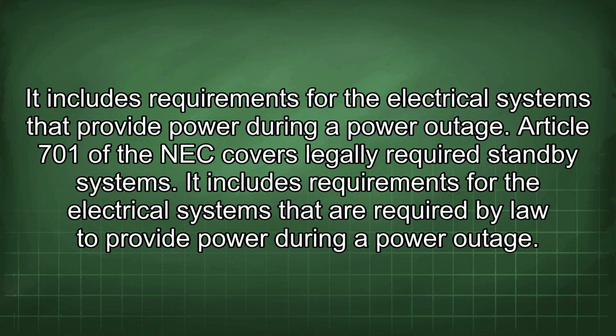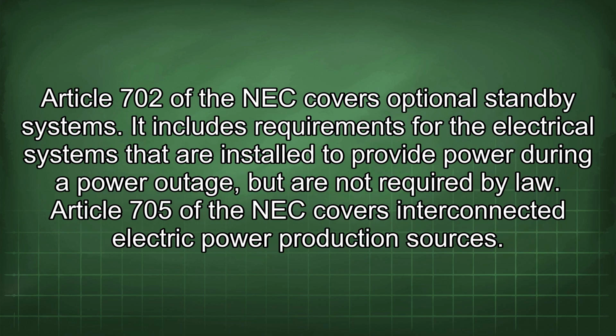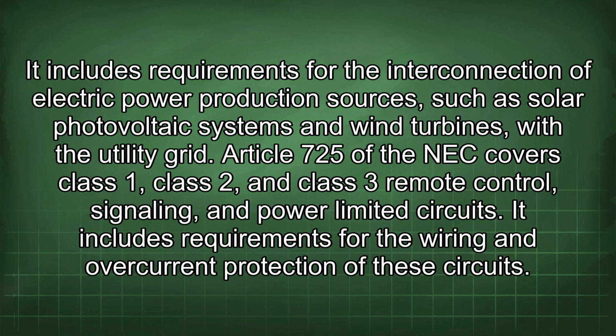Article 701 of the NEC covers legally required standby systems. It includes requirements for the electrical systems that are required by law to provide power during a power outage. Article 702 of the NEC covers optional standby systems. It includes requirements for the electrical systems that are installed to provide power during a power outage but are not required by law. Article 705 of the NEC covers interconnected electric power production sources. It includes requirements for the interconnection of electric power production sources, such as solar photovoltaic systems and wind turbines, with the utility grid.